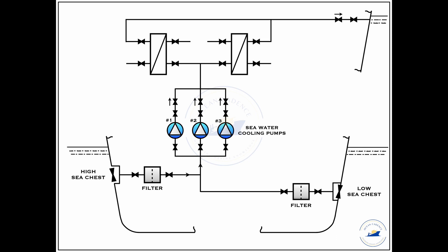However, since the lines are interconnected on most of the vessels, the purpose served is the same. Now these sea cooling water pumps are the ones that are drawing suction from the sea chest for the circulation of the sea water further, and then through the discharge they are sending it into the LT coolers that are present onboard.